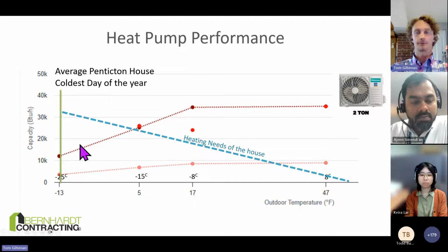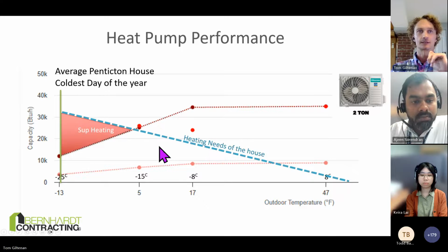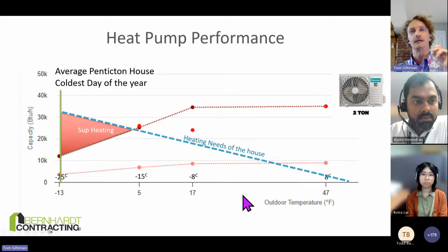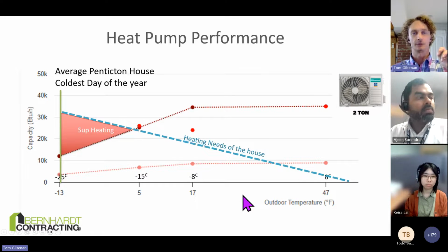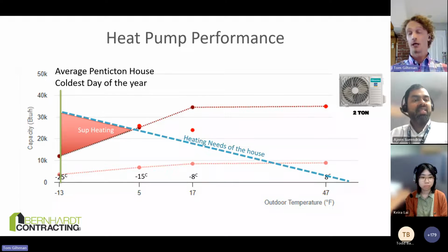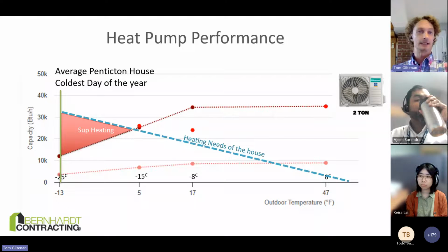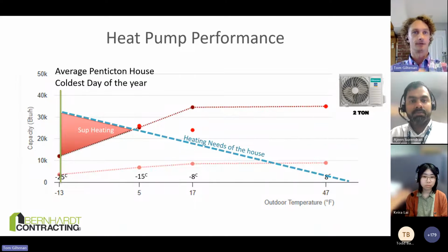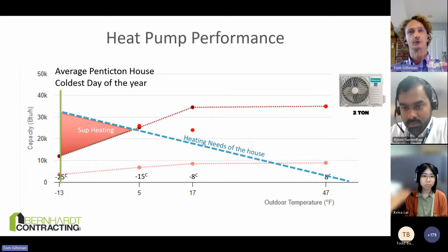the temperatures, or sorry, the efficiency of the heat pump. And where those two lines cross is where you would need supplementing heating. So this is when you would need supplementary heating. So this could be a gas furnace, electric furnace, radiant heat, all of the above. Okay, so that is when you will need supplemental heat.